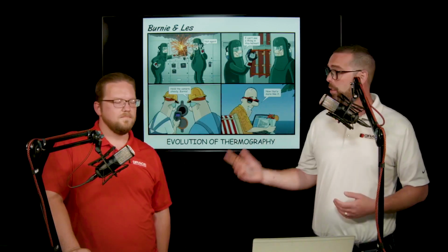Exactly. With the hotspot monitor, it's continuous, fiber optic, and non-conductive. This device can also be seamlessly integrated over Ethernet and Modbus protocol, so that alarm and alert - let this device do the work for you. Let it trend out and baseline your equipment health and help identify anomalous behavior to prevent a thermal avalanche or an explosion, like at that high-rise hotel.